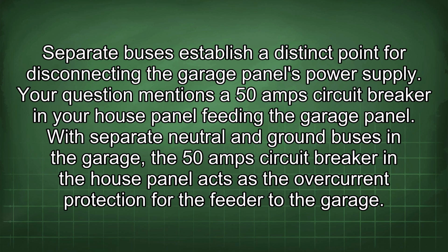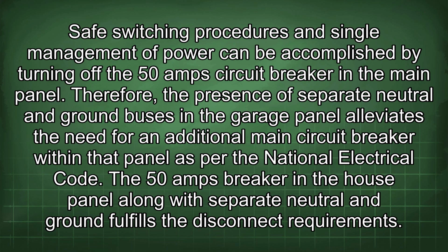Your question mentions a 50 amp circuit breaker in your house panel feeding the garage panel. With separate neutral and ground buses in the garage, the 50 amp circuit breaker in the house panel acts as the overcurrent protection for the feeder to the garage. Safe switching procedures and single management of power can be accomplished by turning off the 50 amp circuit breaker in the main panel. Therefore, the presence of separate neutral and ground buses in the garage panel alleviates the need for an additional main circuit breaker within that panel as per the National Electrical Code. The 50 amp breaker in the house panel along with separate neutral and ground fulfills the disconnect requirements.